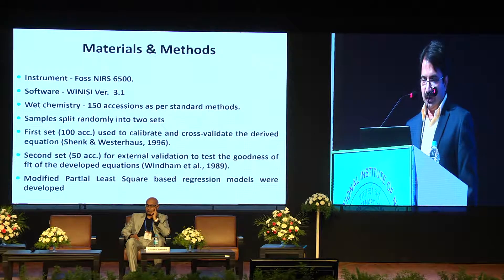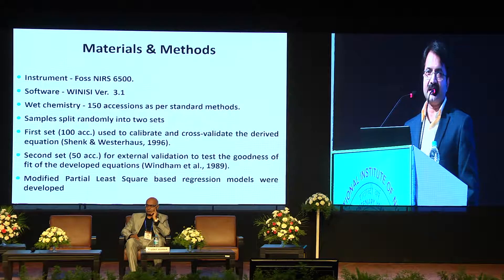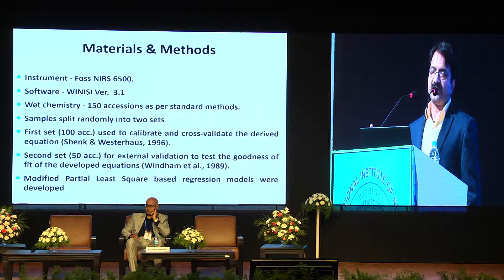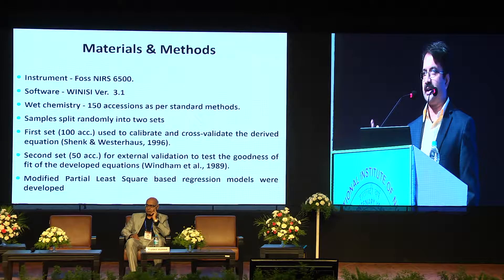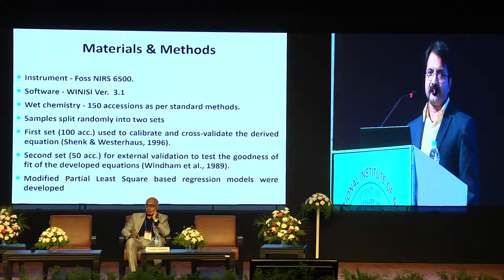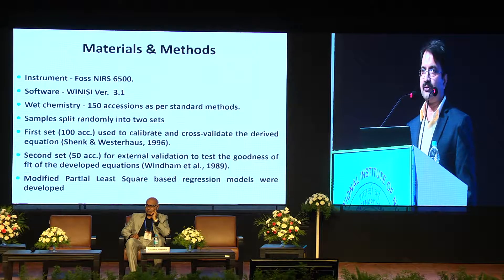We used the instrument FOSS NIR6500 with software WinISI version 3.1. We performed wet chemistry on 150 accessions pre-screened on the NIR, dividing the sample set into 100 samples for developing the calibration equation and 50 samples for validation. The equation generated from the 100-sample set was used to predict values for the 50-accession set, and predicted values were compared with actual lab values to find the goodness of fit.